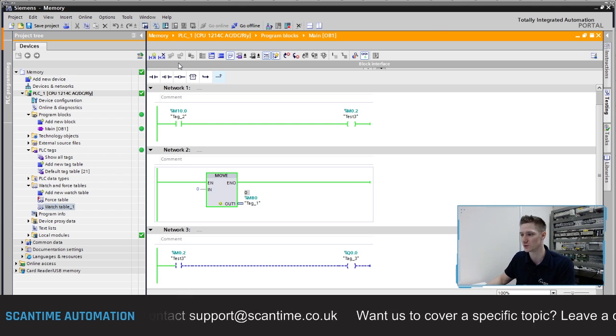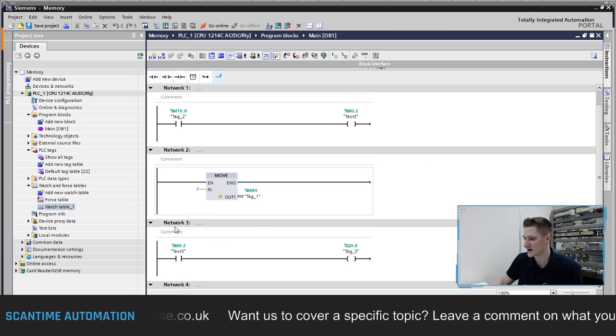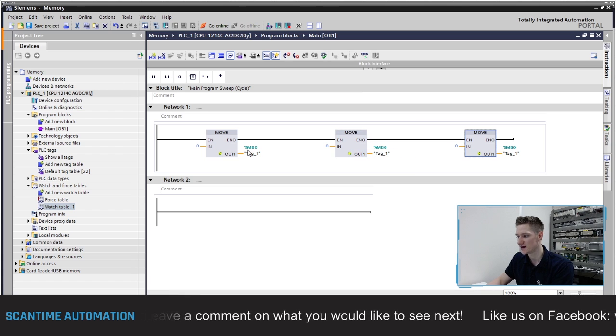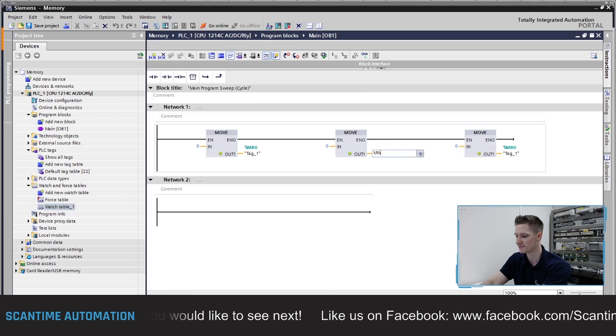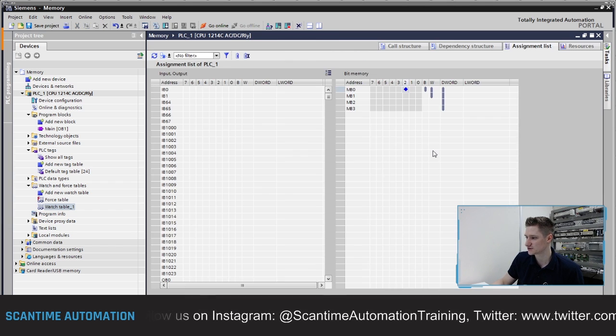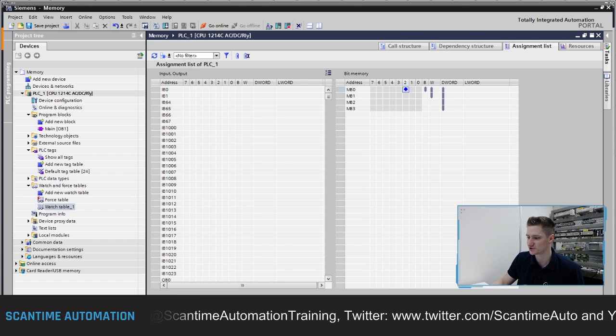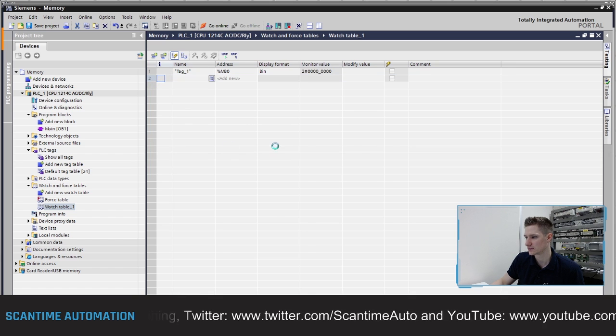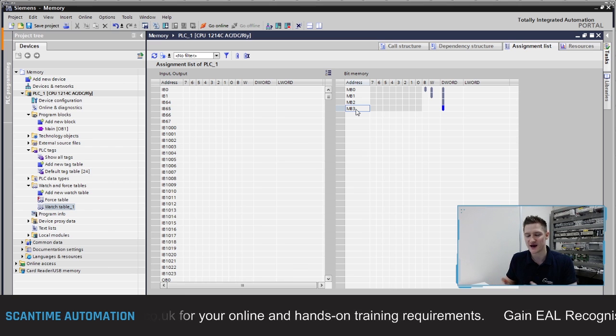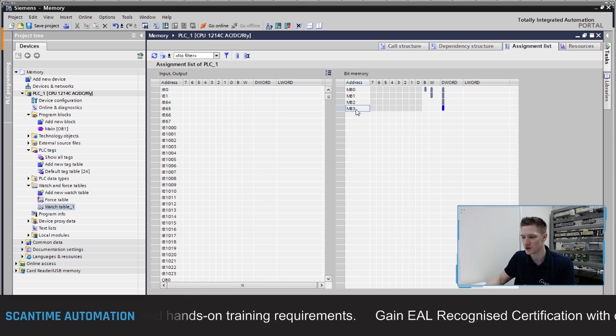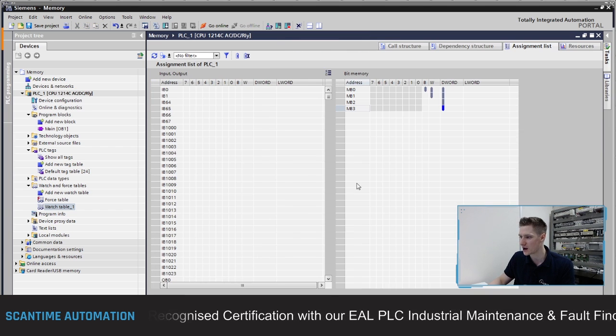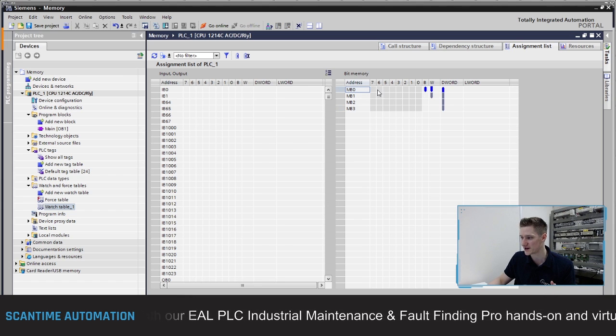That also means you've got to be very careful when addressing words and double words. Let me come offline, delete those networks, and move zero into memory byte zero, memory word zero, and memory double word zero. Looking at the Assignment List, we can now see we're using MB0, MB1, MB2, and MB3 in the program even though I only specified MB0, MW0, and MD0. This is because a byte is just eight bits - MB0 is your first eight bits.